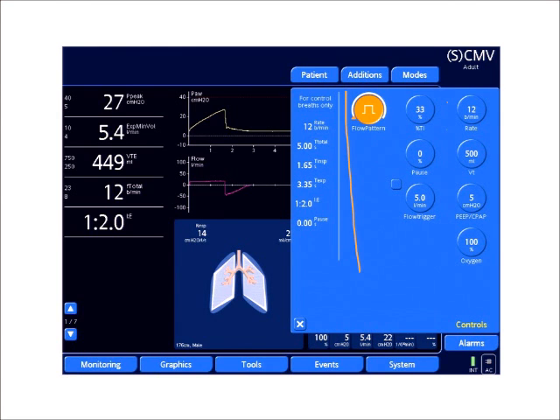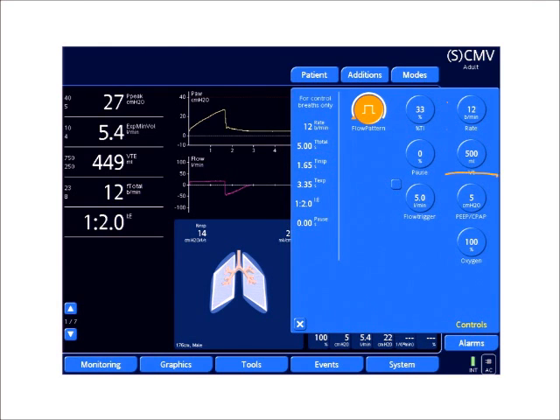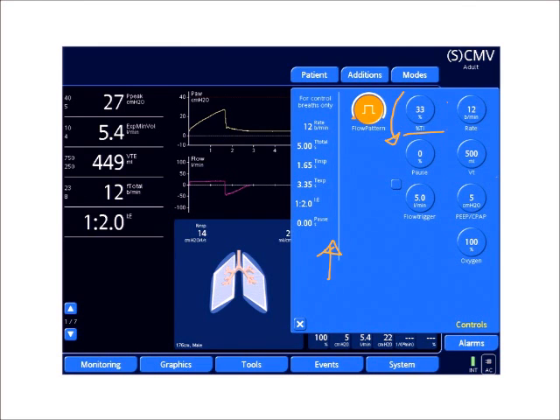If we look at these ventilator settings, the screen is broken down into the settings area and a smart window that will show changes or calculations based on your settings. Down here is my inspiratory time — it doesn't calculate my flow rate directly, but it shows my inspiratory time. So if I increase or decrease my inspiratory time percent, it's going to change my inspiratory time. In this situation, if I wanted to increase my flow rate, I would actually decrease my inspiratory time percent, and that would give me a faster flow rate if the patient needed it.